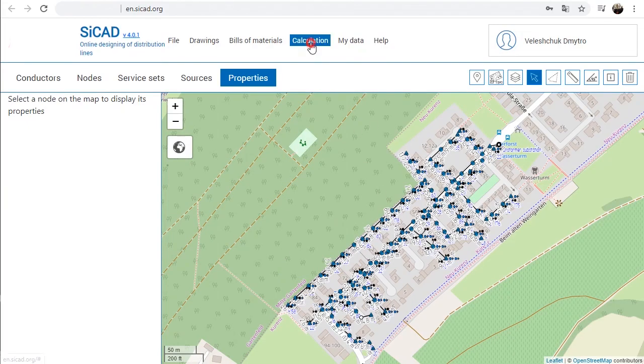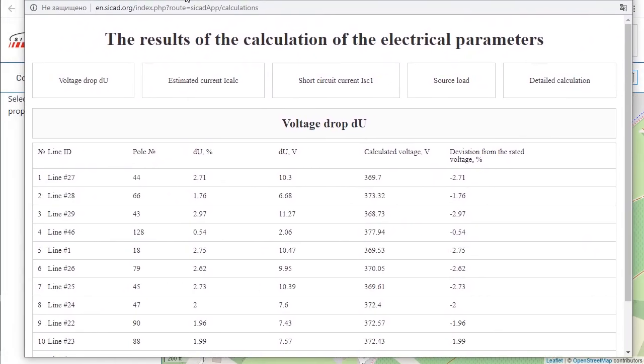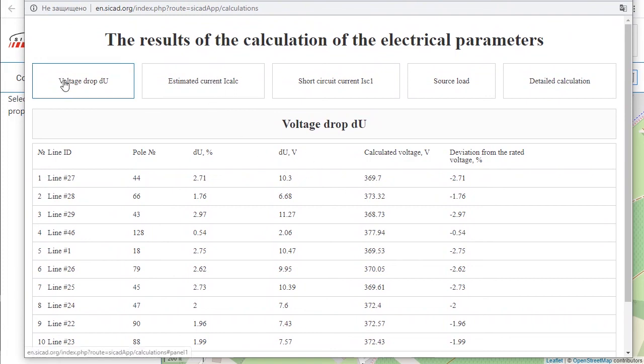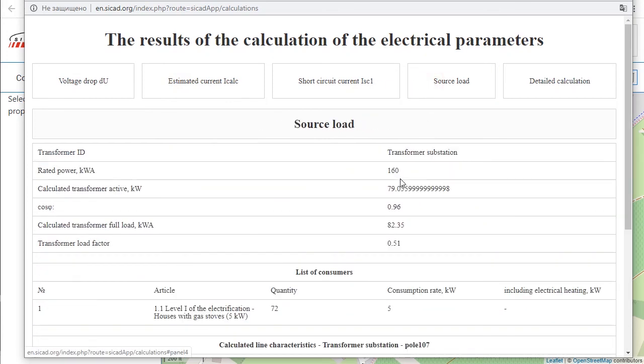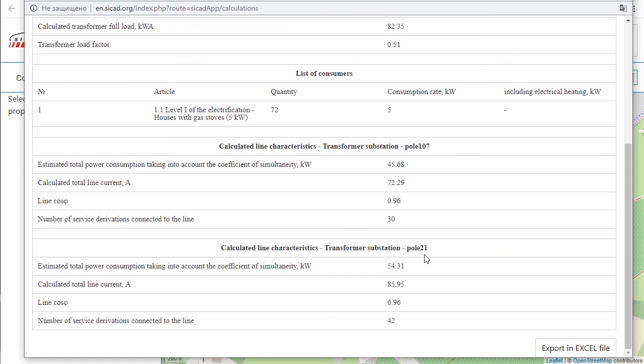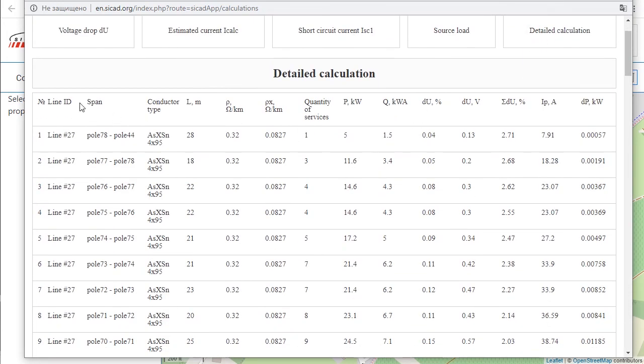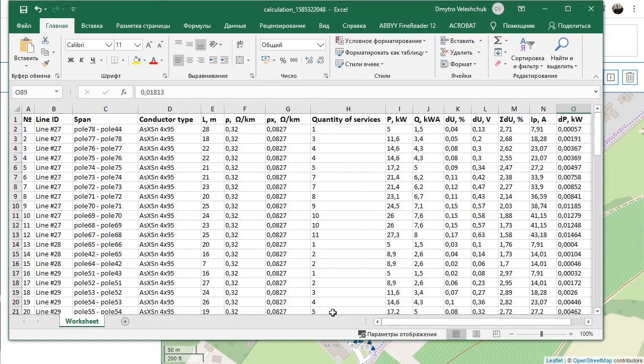To obtain the results of electrical calculations, select Currents and Voltage Drops calculation in the Calculation menu. SiCAD allows electrical calculations of LV networks to be carried out quickly and flexibly. The result of the calculation will be displayed in a modal window with tabs showing: Voltage Drop and Voltage Deviation, estimated currents in each span, the estimated load on the transformer, and the number and types of consumers. The result of the calculation for each line starts from the transformer. The detailed calculation tab provides detailed calculation results for each span. All calculation results can be downloaded in Excel format.